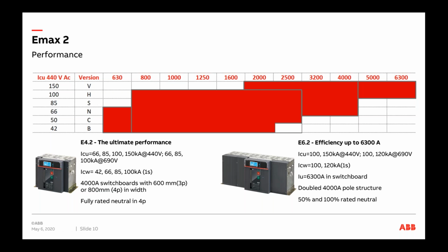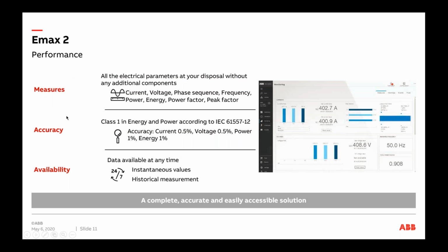That's on the performance. Now, I would like to talk a bit about also the measurement capability. So like I said, we have gone up on the accuracy class. So as per 61557, we look at accuracy of 0.5 and 0.5 for voltage, and power is 1. So that's what we call class 1. We can look at a lot of different measurements, whether it's current, voltage, frequency, power factors, peak factors, harmonics, kilowatt hours, all that is possible through the Emax 2 range. And then the data is available instantaneously, which means that we have quite a high sampling rate of trying to extract any kind of diagnostics or historicals we want to extract from the system, not just to understand how the breaker is functioning, but also be trying to, let's say, analyze data which comes out of the breaker.